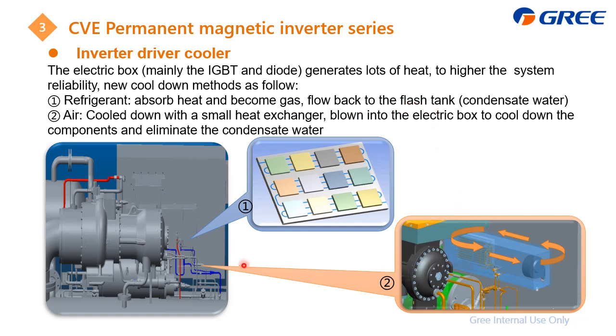Besides, we also have a small size heat exchanger. You can find that this is the small size heat exchanger, and from this one we can also do the cooling, and then use the fan to circulate the air to cool down the electrical box to ensure that it does not overheat.